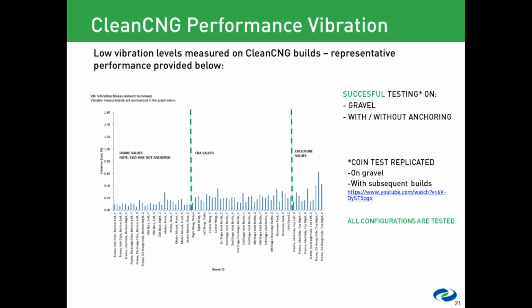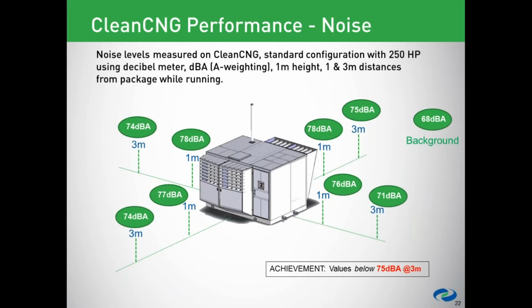Now, as all the technicians out there listening will attest to, of course, compressors can tend to shake themselves loose in many cases, and the further you can reduce the vibration logically, the better your maintenance schedule is going to be, and that was a real key focus, as well as, of course, reducing the noise levels. And speaking of reducing the noise levels, I'll let Brad speak to this diagram here. Sure. So this diagram shows some of the test results of our new compressor package, tested out in the back lot behind the factory.